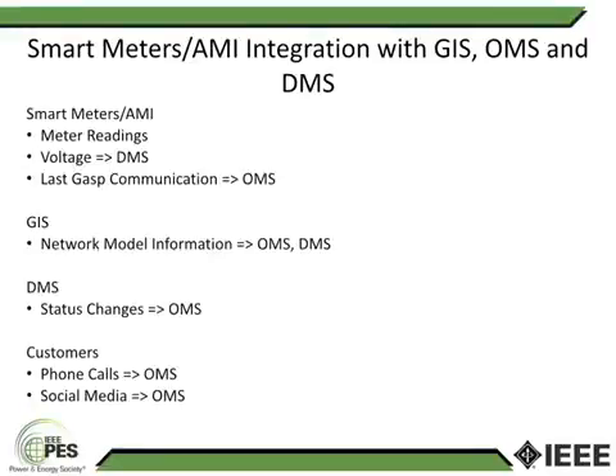Some examples are meter readings from smart meters, but also voltage from smart meters going into the distribution management system. What's the voltage along the feeder, for instance? What's the voltage at the end of the feeder? The reason we need to know that is that in the United States, we're required by law through a standard that the voltage at the customer site, where the electricity is delivered, must be within 114 to 126 volts. 120 volts plus or minus 5%. So certain meters at the ends of long feeders give us that information. And also the last gasp communication. When electricity is lost, there's an outage, there's enough energy left in a smart meter to make one last communication to the utility. We call that last gasp communication. It says, hey, I just lost power, and this is the time it occurred. And we want to make sure that gets to the outage management system.